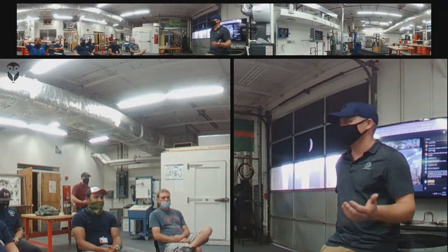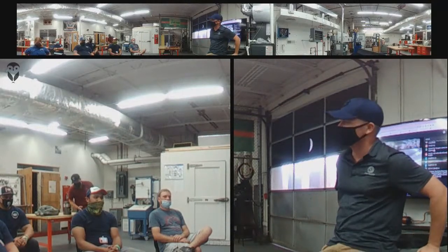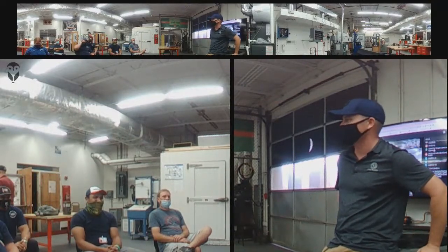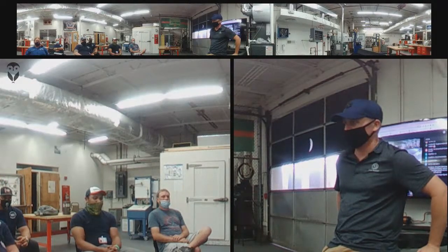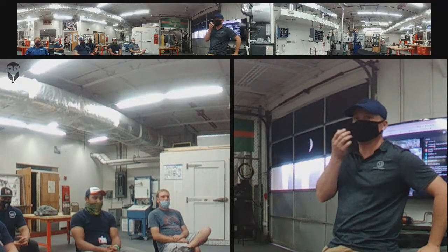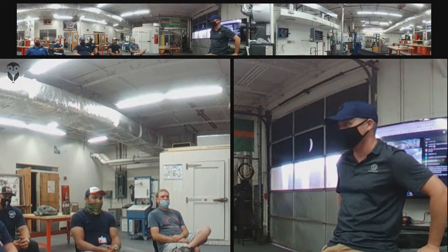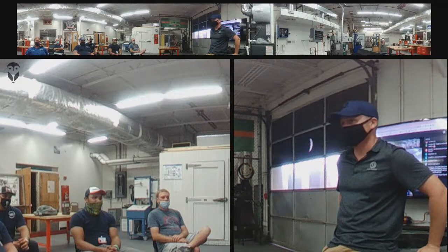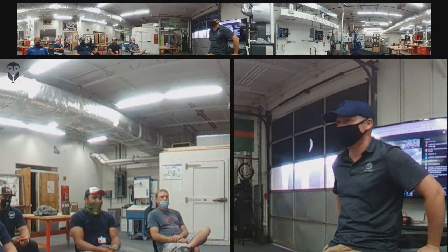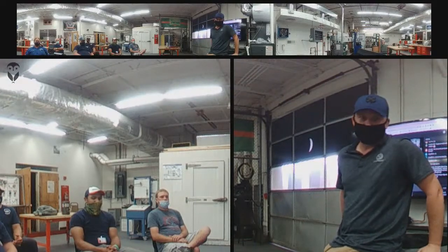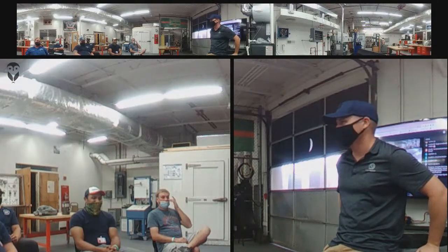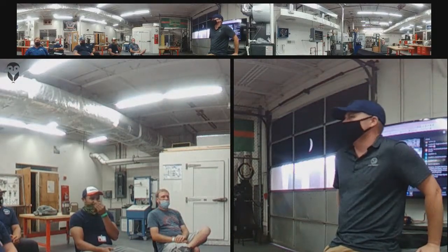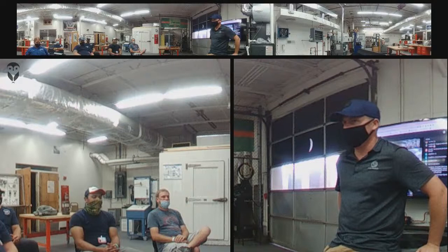I've seen grocery stores where they've been running sprinklers on them for months, and that's a really bad idea because you're going to put deposits on the coils, and they're not going to transfer heat. But in terms of an emergency way of getting a piece of equipment up and running, those big slab condensers, just run water on them. Now, again, there are certain markets where that is heresy, and you absolutely can't do that. I'm sure some of our Nevada and California people are screaming right now, but in our market, it's a temporary way to get something up and working.